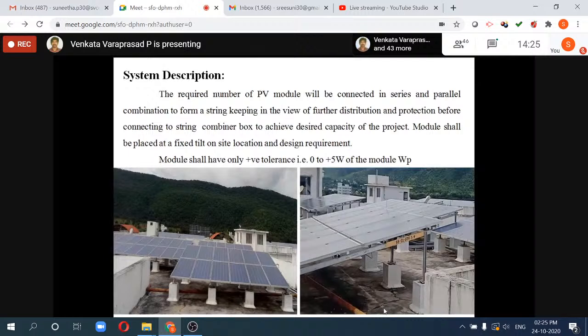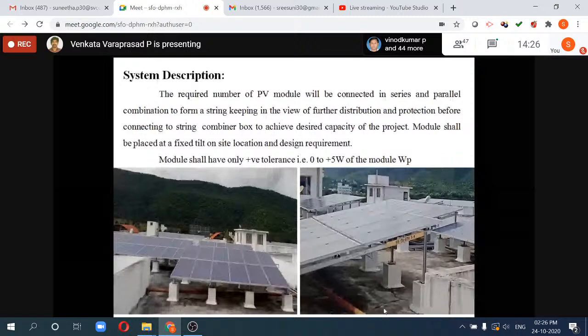And here, the required number of PV modules will be connected in series. A basic concept: if you want to increase the DC voltage, take batteries. If you want to increase the voltage level, the number of batteries are connected in series. If each battery has 10 volts and the desired output is 40 volts, then four batteries are connected in series. If the series connection is one set and there are 10 sets, then the 10 sets are connected in parallel, because the total system will maintain the common 40 volts.